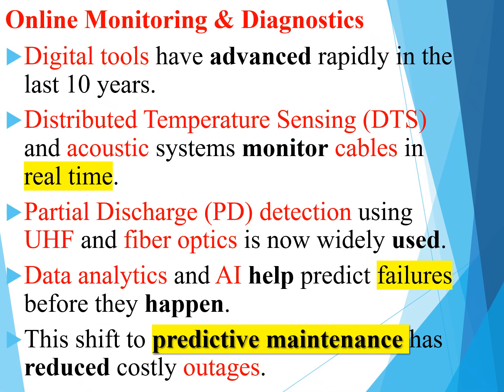Regarding online monitoring and diagnostics, digital tools have advanced rapidly in the last decade. Distributed temperature sensing and acoustic systems monitor cables in real-time. Partial discharge detection using UHF and fiber optics is now widely used.